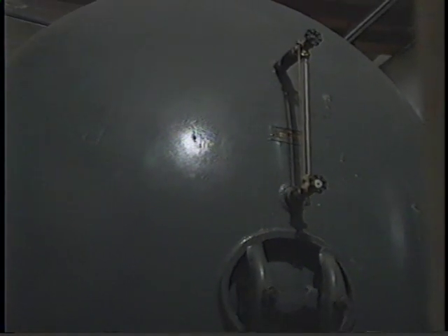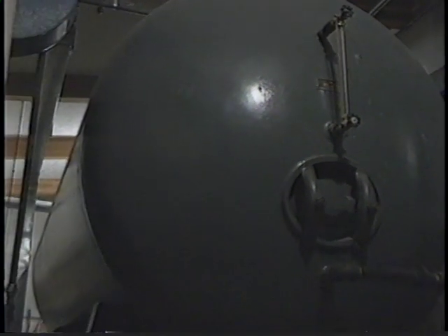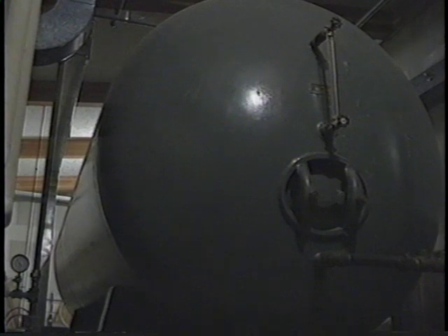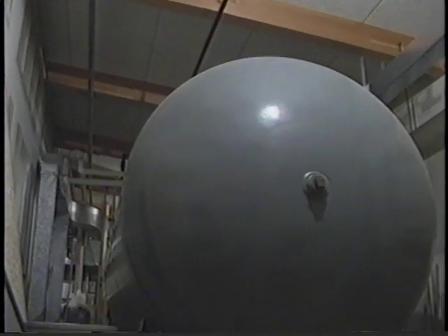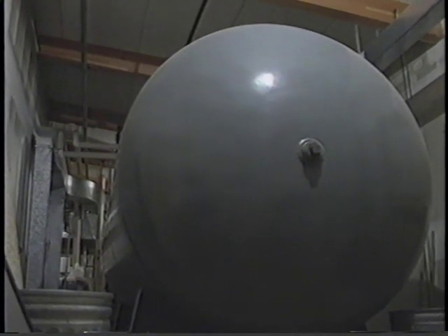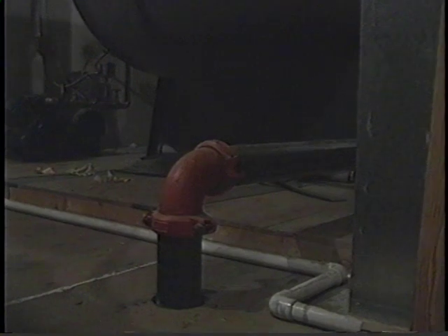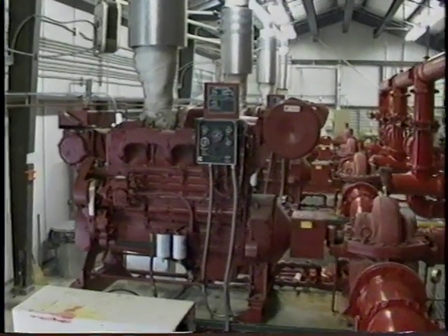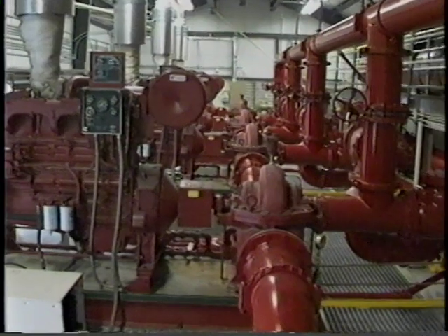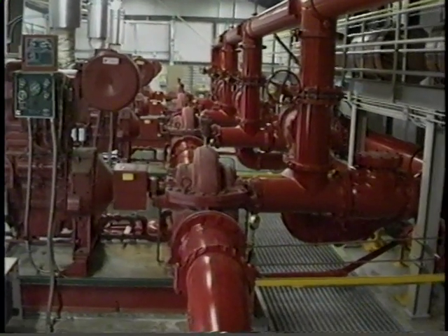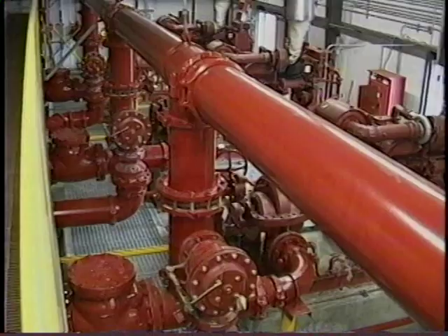Pressure tanks are another source of water supply, and they are used in connection with the secondary supply. Pressure tanks are normally located on the top floor or on the roof of the building. This type of tank is filled 2/3 full of water, and it carries an air pressure of at least 75 pounds per square inch. If a secondary water supply is needed, a fire pump that takes suction from a static source, such as a large reservoir, can be used.